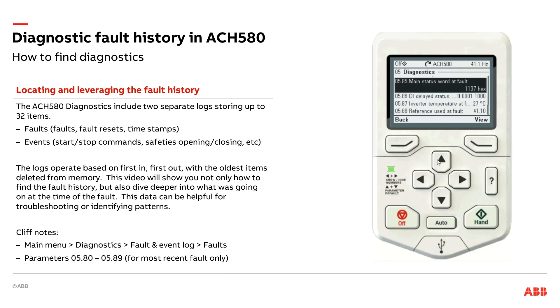So that's in Group 5 of diagnostics. If you like parameters and you're used to going straight there, you're very welcome to go into the diagnostics group when troubleshooting. But I like to be able to look at the whole history of faults that have occurred, so I prefer going to that event and fault logger in diagnostics and diving into it right there on the ACH 580 drive. If you've got any questions, feel free to reach out to your local ABB drive specialist or your ABB factory regional application engineer. Thank you.